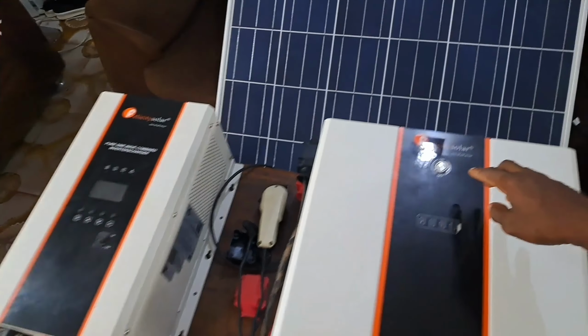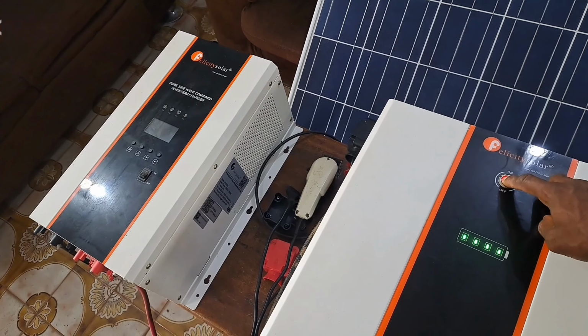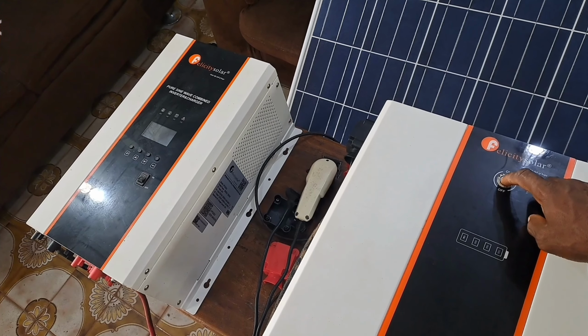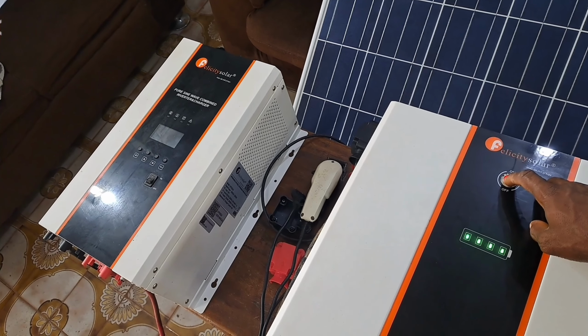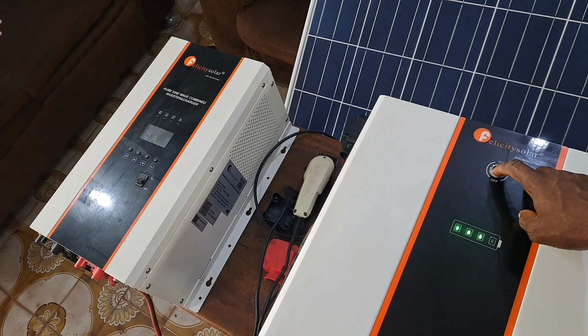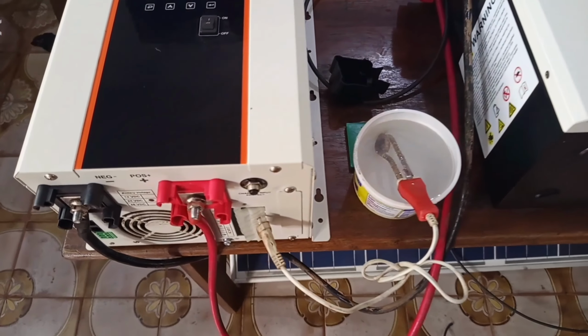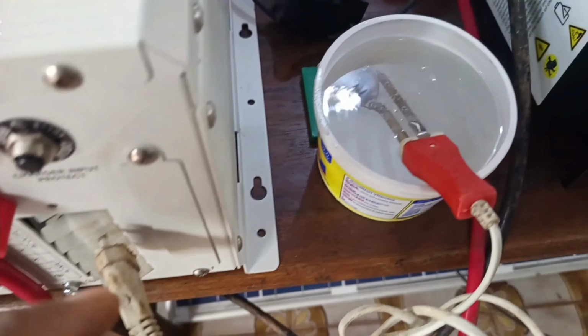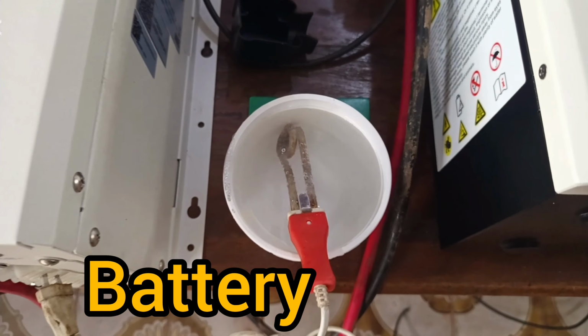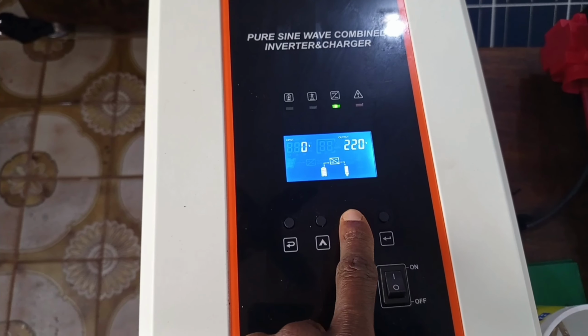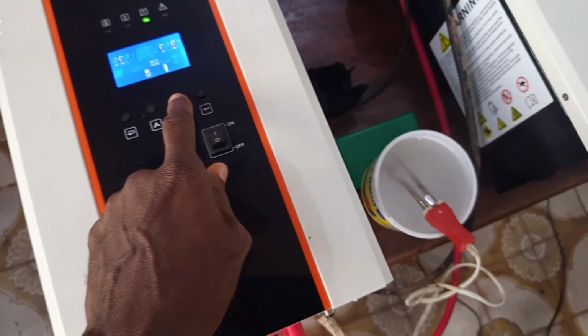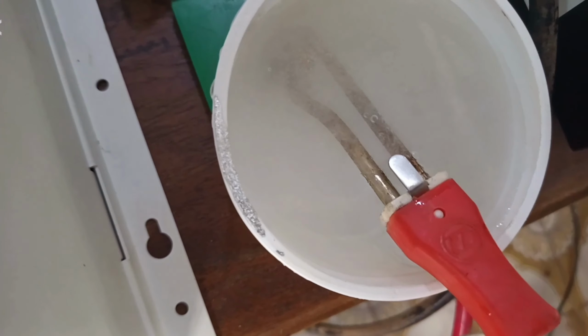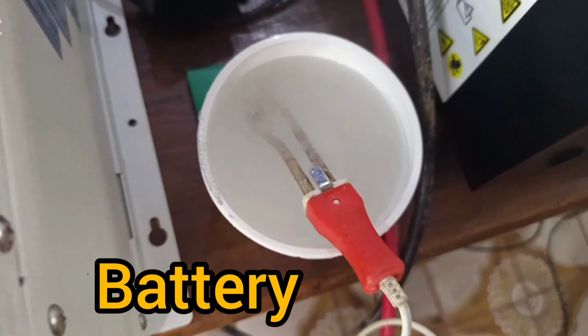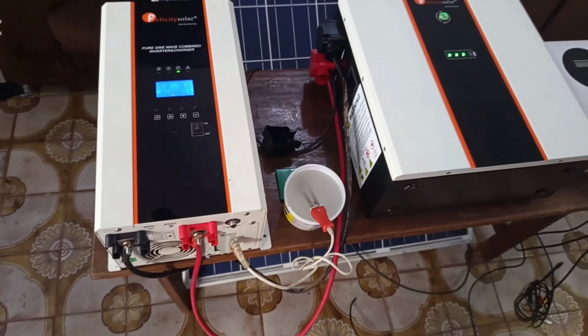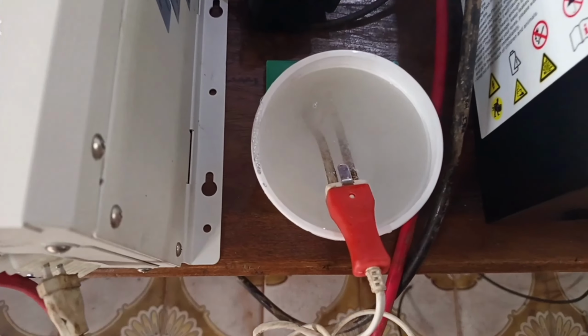If I put 2000 watts on my 5 kilowatt hour lithium iron phosphate battery, it's going to shake it a bit in terms of the composition inside, because I'm putting a heavy load on a seemingly small battery. But if I put that same 2000 watts on a 10 kilowatt hour battery, it won't be able to shake it, because the power isn't very strong compared to the size. Now if you put that 2000 watts on a 15 kilowatt hour battery, it's going to look like peanuts to it. So if you know you'll be using heavy loads on your inverter, it's something to consider, because you want to put a small load comparatively to your battery size. Very important.